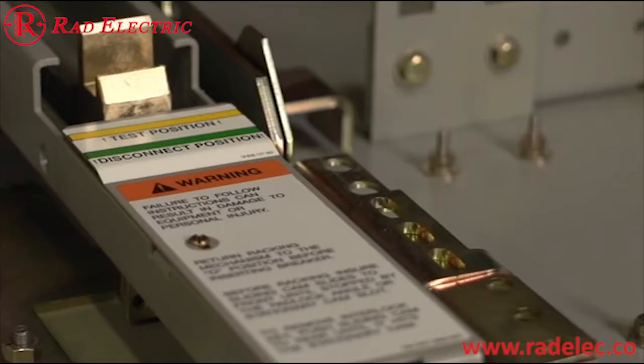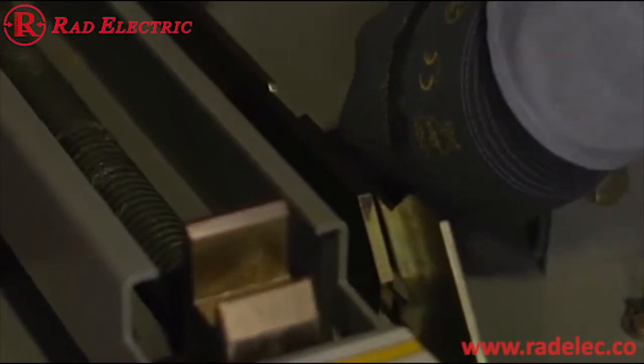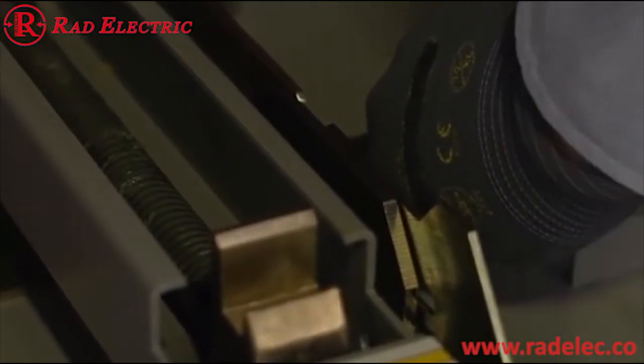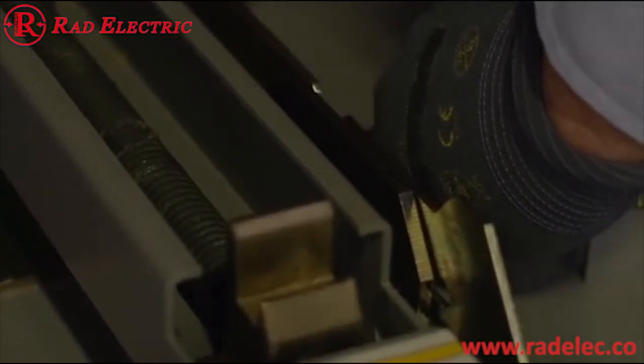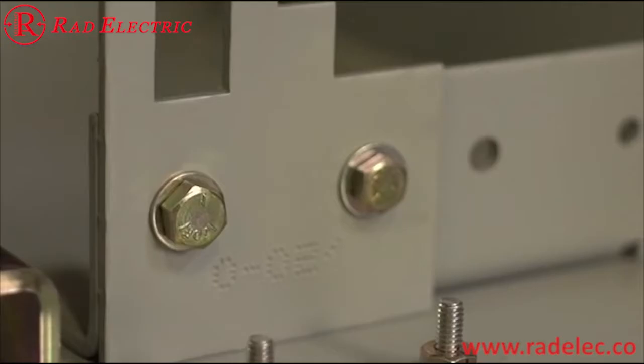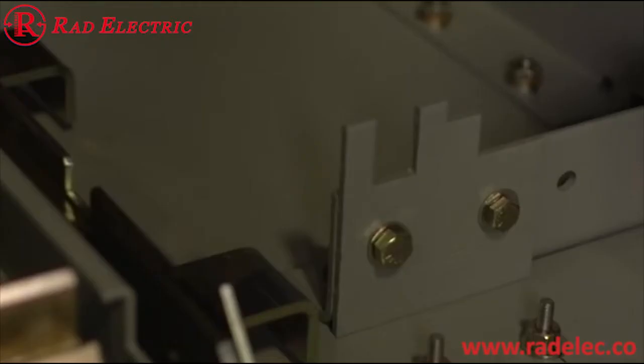circuit breaker. Next to the racking mechanism is a sliding cam plate. It has a padlock provision, so up to 3 padlocks can be installed to prevent closing of the circuit breaker. This is the worm gear. It's important that this stays lubricated. If additional grease is required, please contact Siemens. Next, we have the interference blocking plate, or coding interlock, which prevents the incorrect size circuit breaker from being inserted into the cell. And to the right of that is the interference plate position, which is used as an option if special interlocking is needed for an electrically operated ground test device.